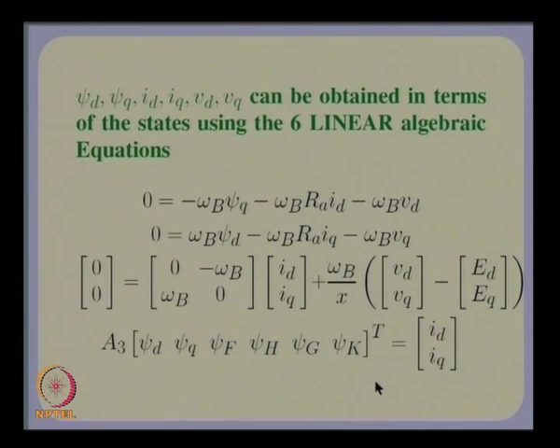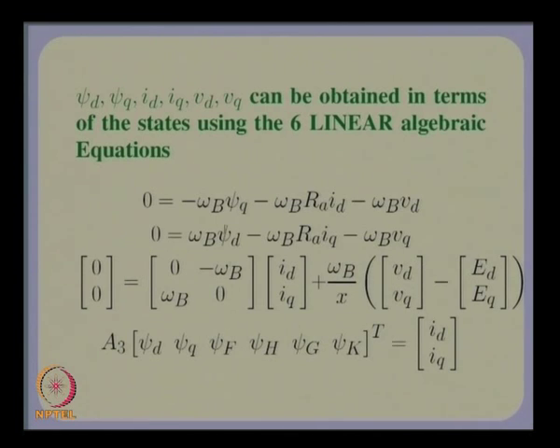The variables ψ_h, ψ_g, and ψ_k appear here. This is how we obtain all the equations: a mixture of six differential equations and six algebraic equations. The algebraic equations allow us to write V_d, V_q, I_d, I_q in terms of the states. Since V_d, V_q, I_d, I_q are required by the differential equations, and are expressible in terms of the states ψ_f, ψ_h, ψ_g, ψ_k, δ, and ω, it is a fairly straightforward matter to substitute and eliminate them from the differential equations.